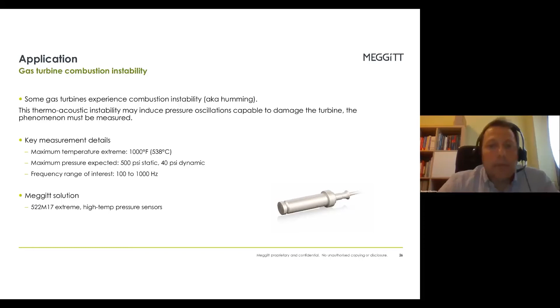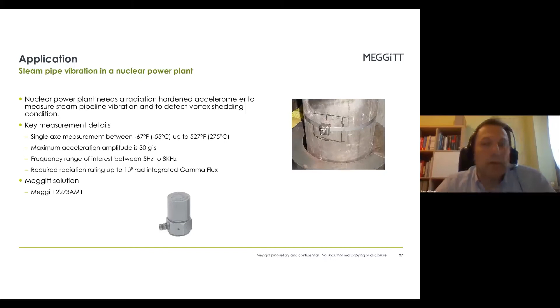The second application is quite common for the primary circuits of a nuclear power plant: pipe-type vibration monitoring. What's requested here is for the installed unit to resist for a number of years inside the radiation environment, so we need radiation resistance to gamma flux. The solution we usually provide is the 2273 or the 2276, which has similar resistance.